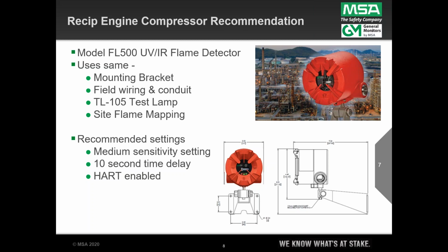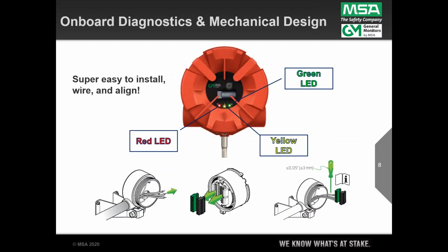Baseline recommended settings for this instrument on most projects, or most compressor stations, are the medium sensitivity setting, unless there is a need for longer range, a 10-second time delay, and then HART enabled, of course, to allow the field techs to establish communication with the device on the 4 to 20, if that's being routed back to an AI card on the PLC, and then they can talk to it in real time to look at diagnostics or whatever. And speaking of diagnostics, this device has some nice features here. In addition to the HART protocol, for the routine visual inspection, the three LEDs are really useful, where green is good. Yellow would mean there's a trouble condition of some type. Normally it's a dirty window, but it could be low voltage or some other problem. And then if there's an alarm state, you have the red LED, and obviously if it's on red, then there's something being detected at that point.